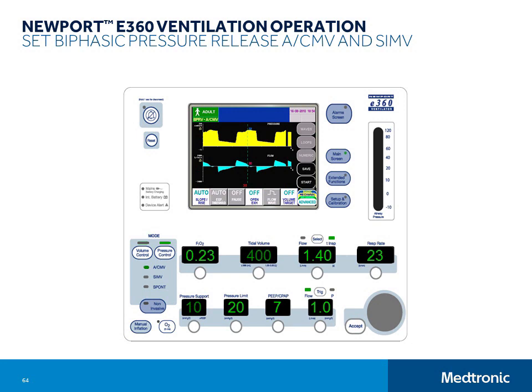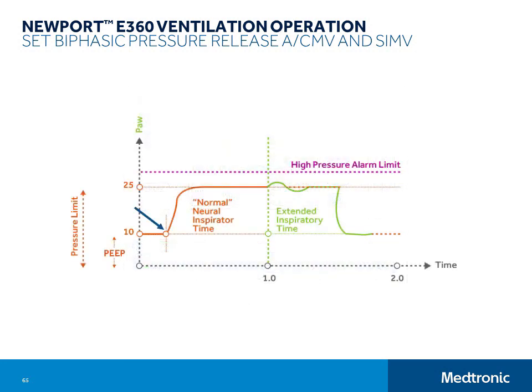You will set inspiratory time in the same way you would set T-high or timed insp on another product. You will set respiratory rate to determine expiratory time or T-low. Set pressure limit in the same way you would set P-high or IPAP, and set PEEP in the same way you would set P-low or EPAP. As with regular pressure control breaths, slope rise determines the assertiveness of the pressure rise at the onset of the breath, and the inspiratory time determines the duration of time that pressure is held at the pressure control level. The difference is that with pressure release breaths, the patient may breathe in or out at any time while pressure is maintained at the pressure control level.